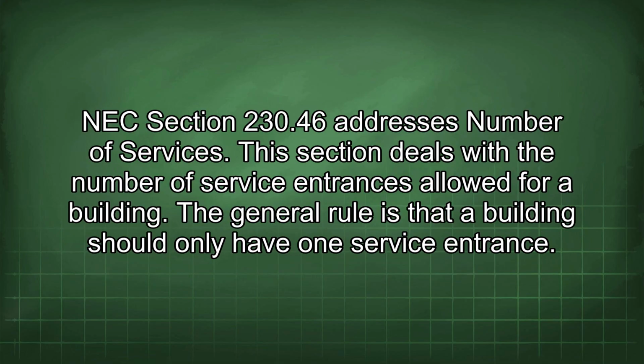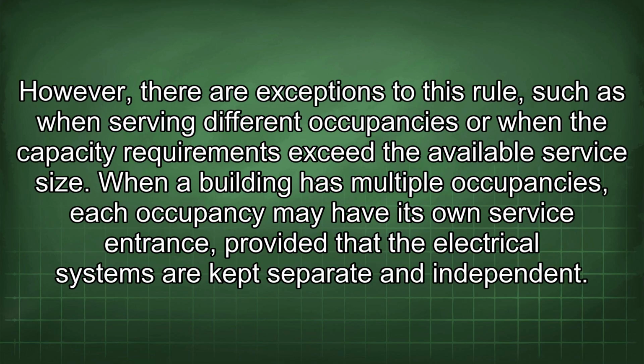NEC Section 230.46 addresses number of services. This section deals with the number of service entrances allowed for a building. The general rule is that a building should only have one service entrance. However, there are exceptions to this rule, such as when serving different occupancies or when the capacity requirements exceed the available service size. When a building has multiple occupancies, each occupancy may have its own service entrance provided that the electrical systems are kept separate and independent.